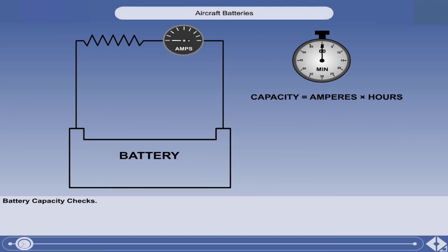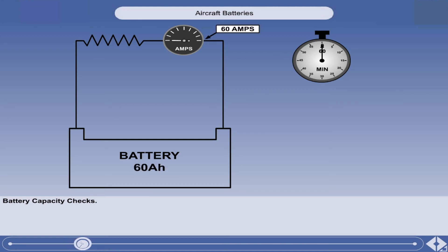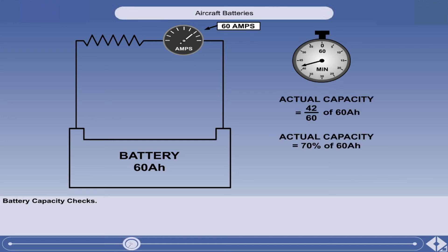The capacity of a battery is the product of the load in amperes that the manufacturers state it will deliver, and the time in hours that the battery is capable of supplying that load. The capacity is measured in ampere-hours. Actual capacity is determined by the battery's deterioration in service. If a 60 ampere-hour battery, when subjected to a 60 ampere load, lasts only 42 minutes, then the actual capacity is 42 sixtieths, or 70% of its rated capacity. In other words, the battery is only 70% efficient.